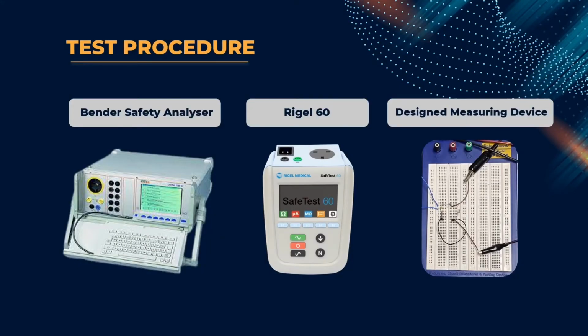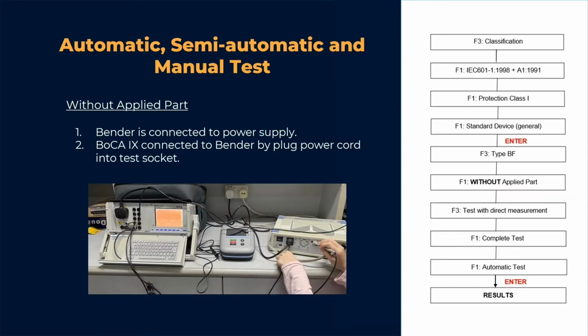Hi, my name is Naili. For the test procedure, we will use these 3 devices to determine the leakage current, which are the Bender safety analyzer, Rigel 60 and our own designed device circuit. First, for Bender, we are doing automatic, semi-automatic and manual tests for both without and with applied part. Bender was turned on and the bioimpedance BOCA was connected to Bender by plugging the power cord into the test socket. The difference between without and with applied part is the classification on the main menu screen of the Bender.